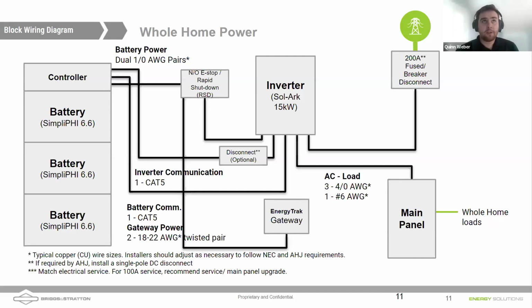So PCS is part of the CRD of UL 1741, and what it allows you to do is basically limit the amount of backfeed to the grid while still allowing us to push a lot of power to your loads. So for instance, on a 100 amp panel, you're only allowed to push 20 amps of power into that panel. But when installed with our CTs around the main feeds, our CTs are dynamically measuring the amount of current that's going into that busing. You can actually set the inverter so that you make sure that busing is never being overloaded.